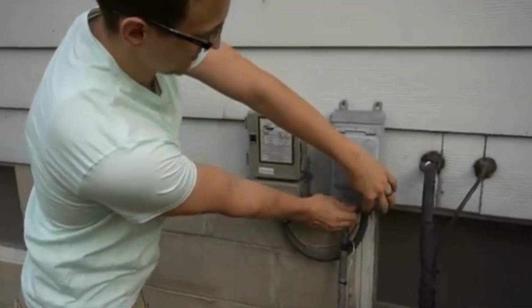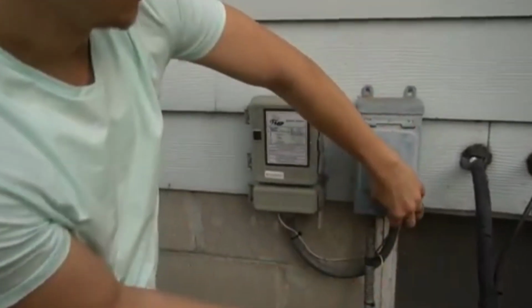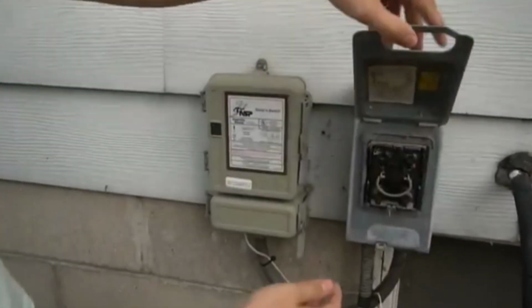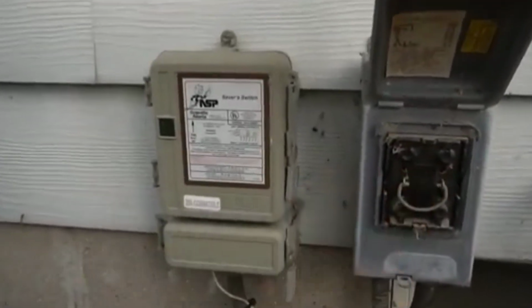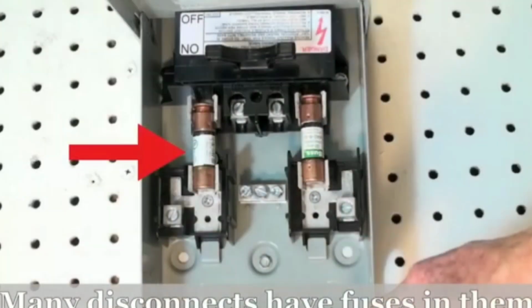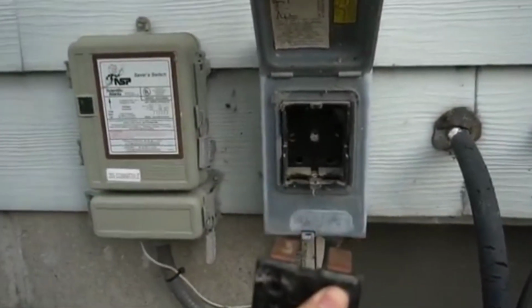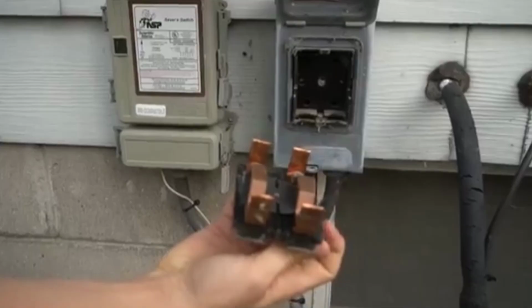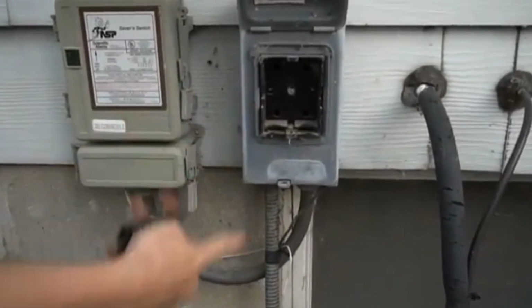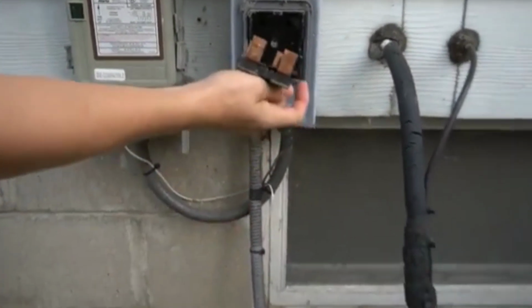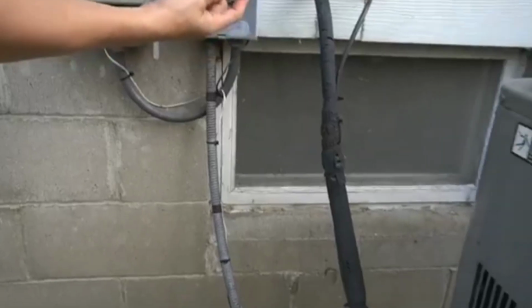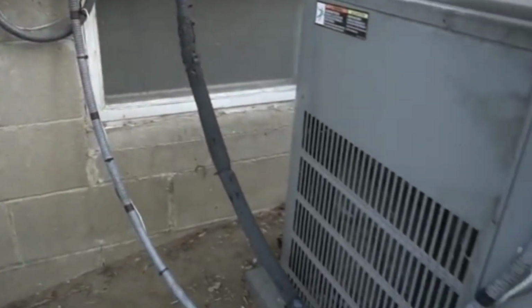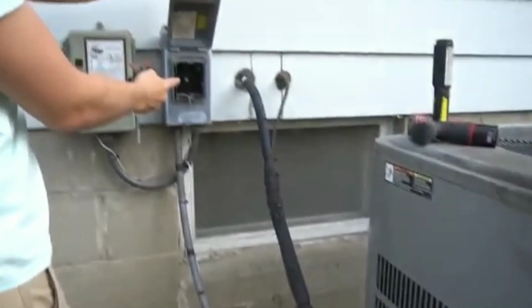If you open it up, most of them will have the pull style plugs. Some of them will actually be a breaker. There's different styles, but most of them are going to be a plug like this that you just yank out. When you yank this out, that disconnects the power going to your condenser unit, the 240 volts. But just to be safe, I would also turn off the circuit breaker for your air conditioner.